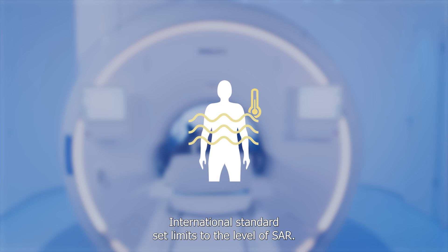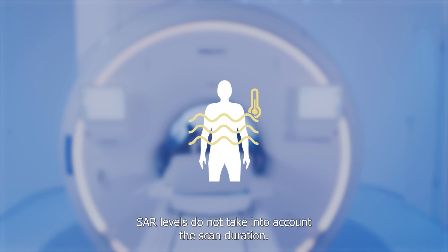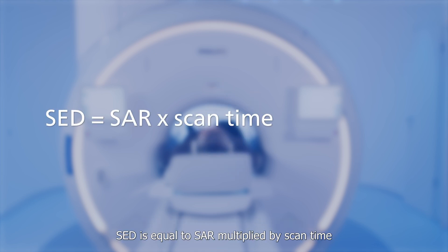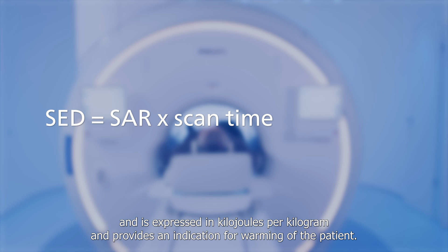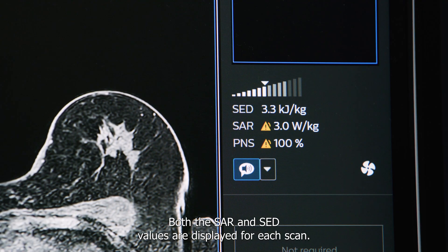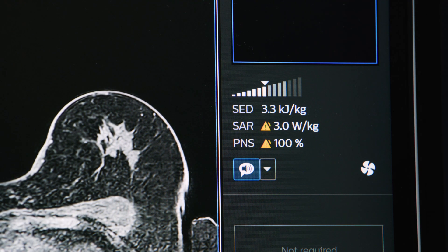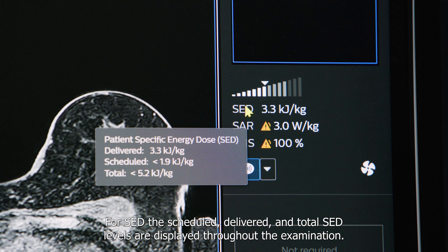International standards set limits to the level of SAR. SAR levels do not take into account the scan duration. SED is equal to SAR multiplied by scan time, expressed in kilojoules per kilogram, and provides an indication of warming of the patient. Both SAR and SED values are displayed for each scan. For SED, the scheduled, delivered, and total SED levels are displayed throughout the examination.